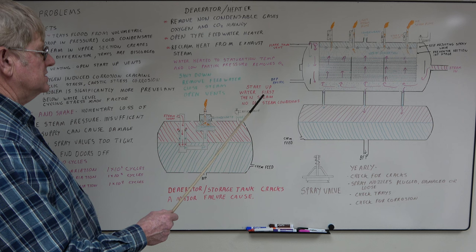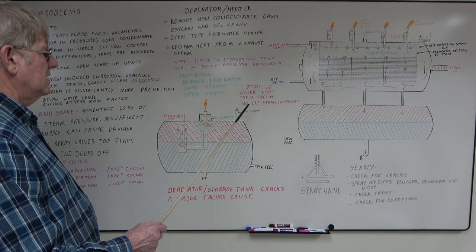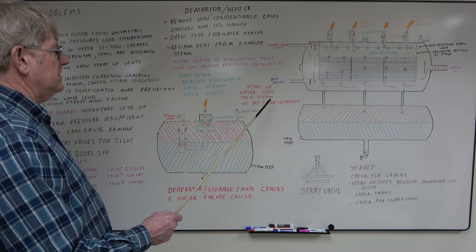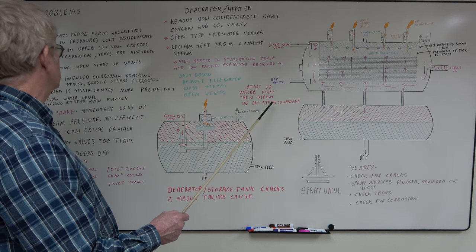Start up. You want water first and then steam. You want to slowly heat them up. You do not want to fill them full of steam, then hit them with water. It could be catastrophic damage to the deaerator.